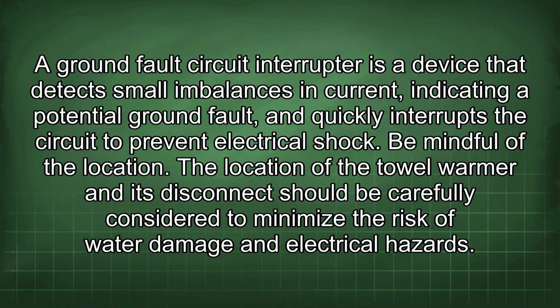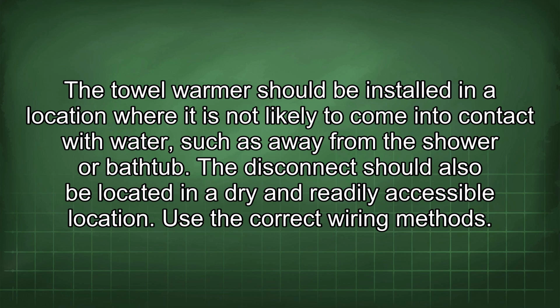Be mindful of the location. The location of the towel warmer and its disconnect should be carefully considered to minimize the risk of water damage and electrical hazards. The towel warmer should be installed in a location where it is not likely to come into contact with water, such as away from the shower or bathtub. The disconnect should also be located in a dry and readily accessible location.